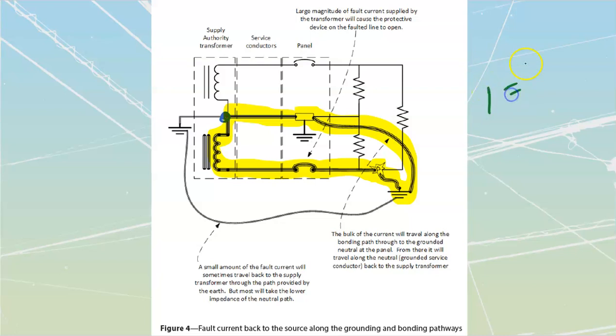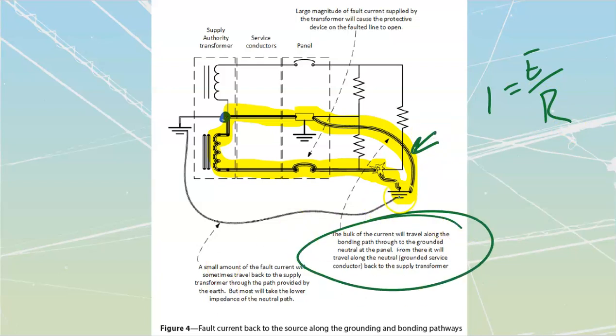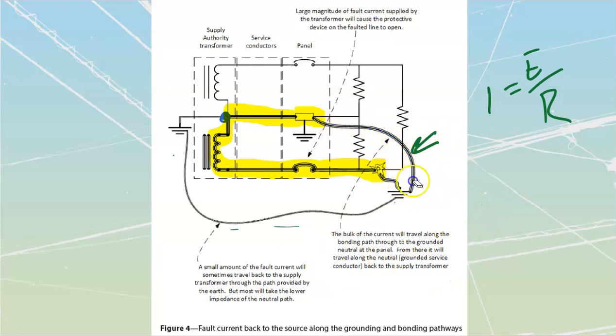Once again, I is equal to E over R. The bulk of my current travels along this path over here, and only a tiny little bit of current will travel through the actual dirt itself and the earth all the way back out to either my supply ground at the transformer or my ground at the panel, wherever those grounds would be. But the bulk stays on the bonding path.